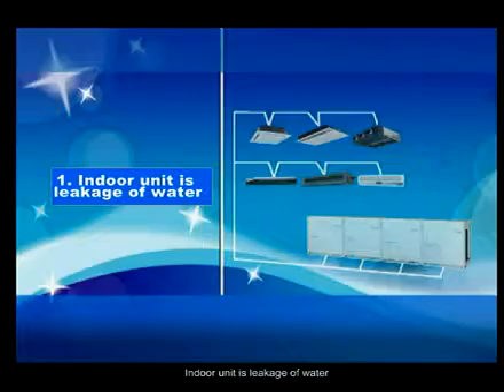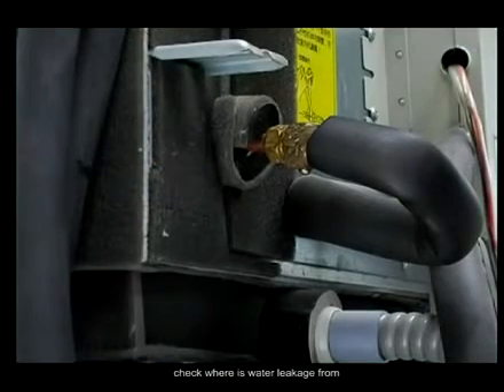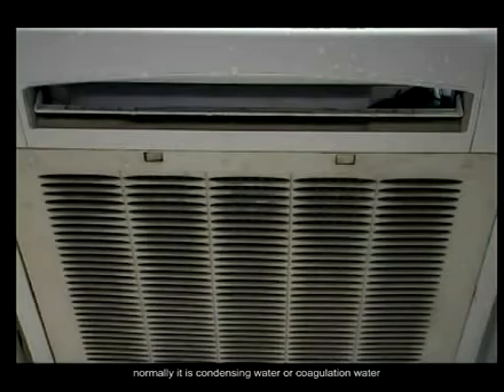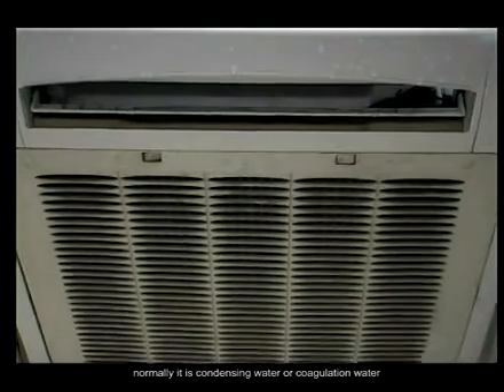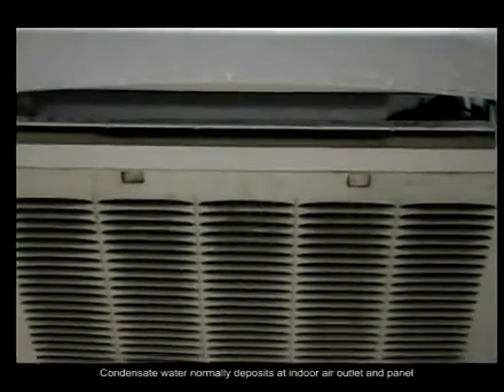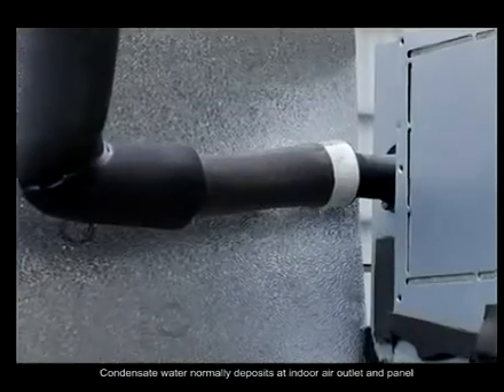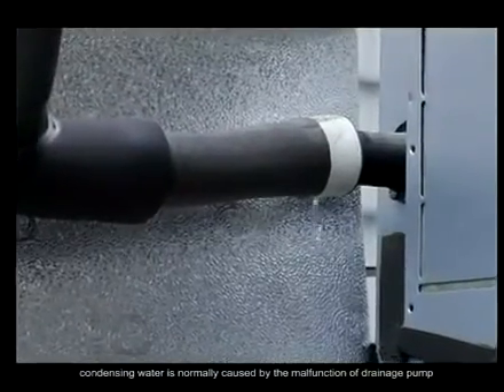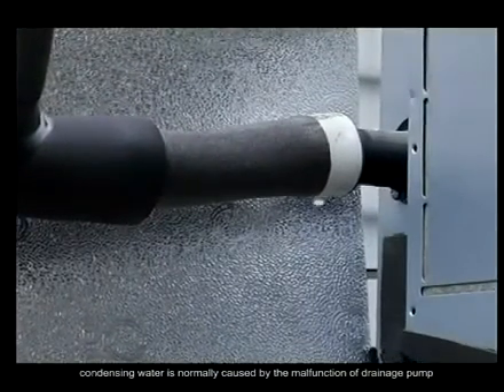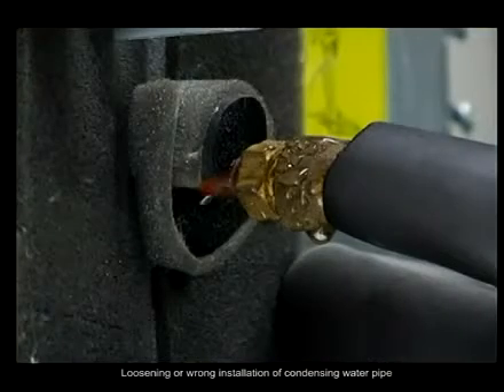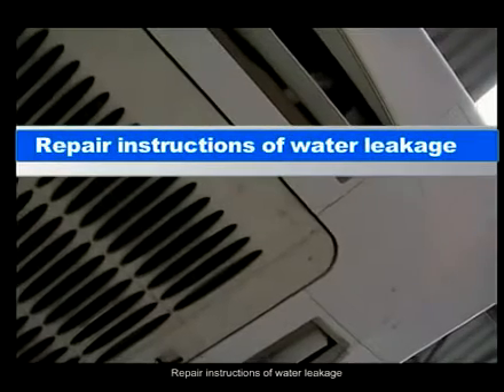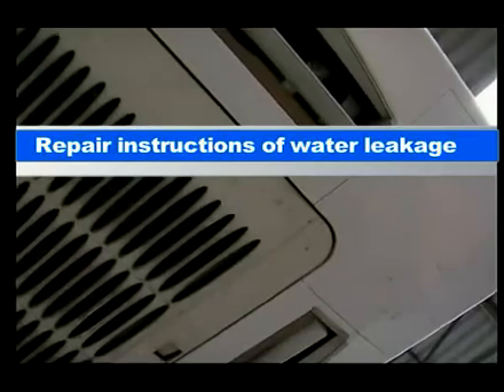Indoor unit is leakage of water. Check where the water leakage is from, normally whether it is condensing water or coagulation water. Condensate water normally deposits at the indoor air outlet and panel. Condensing water is normally caused by the malfunction of the drainage pump, loosening or wrong installation of the condensing water pipe. Repair instructions of water leakage.